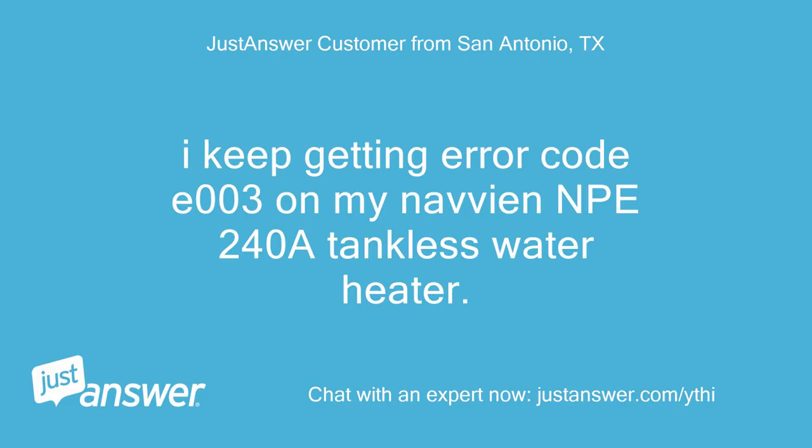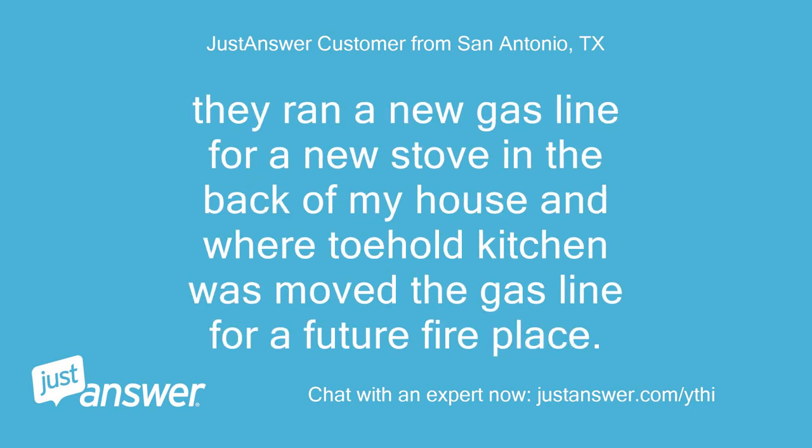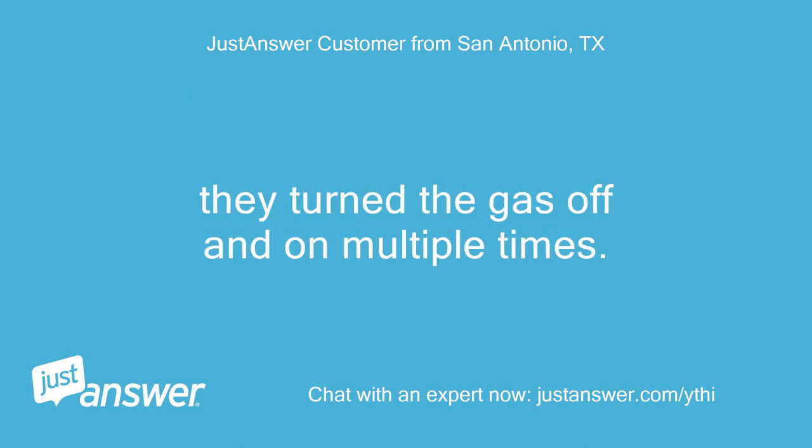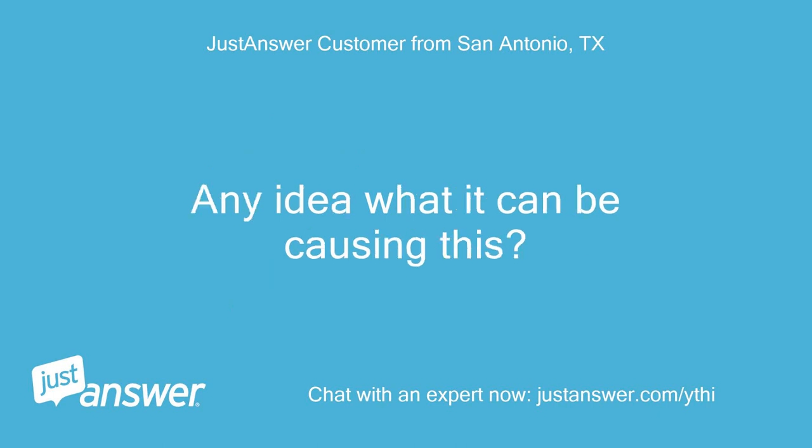I keep getting error code E003 on my Navien NPE 240A tankless water heater. It is about 7 years old and the problem started when I had major renovation work done at home. They ran a new gas line for a new stove and moved the gas line for a future fireplace, turning the gas off and on multiple times. All added gas lines were after the water heater, and the error code comes back usually within a week after a reset.